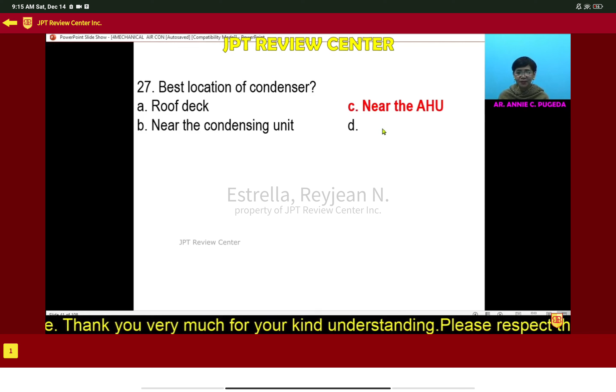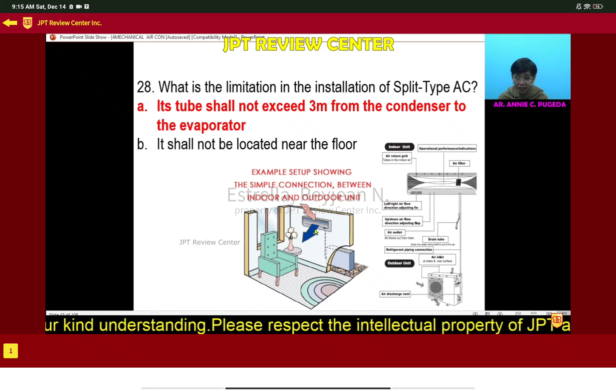Best location of condenser - if you have a split type, what do you do? You place it close to the AHU. Sometimes the multiple choice surprises you, but once you analyze it, that's just it. Limitation, as I've said: its tube should not exceed 3 meters from the condenser to the evaporator, like what we're seeing here - a simple connection between indoor and outdoor unit.